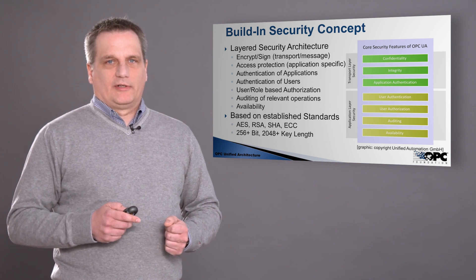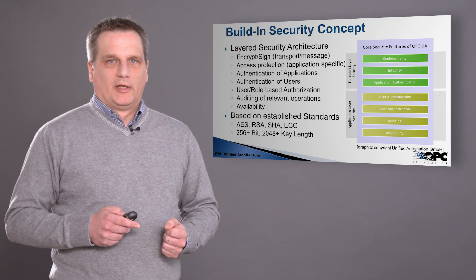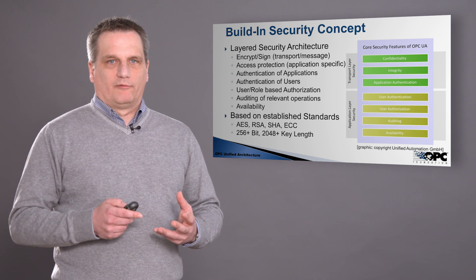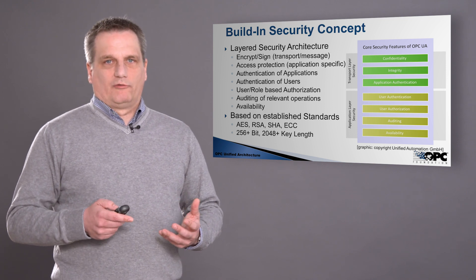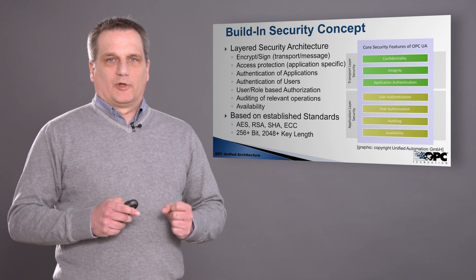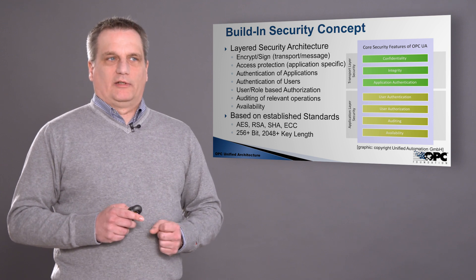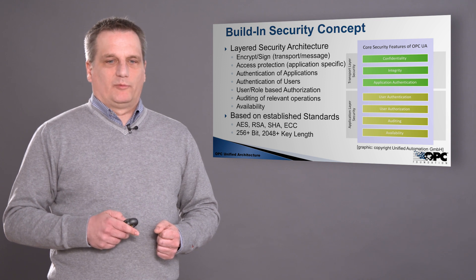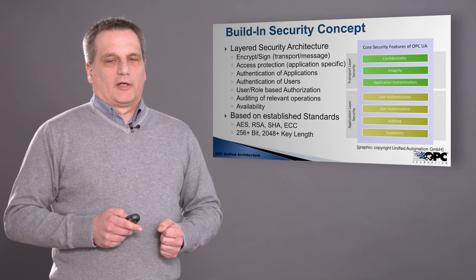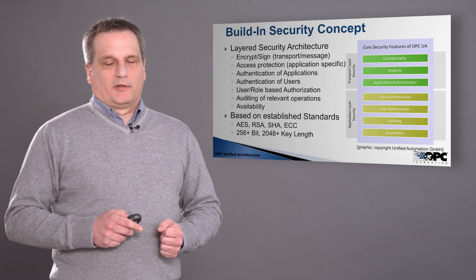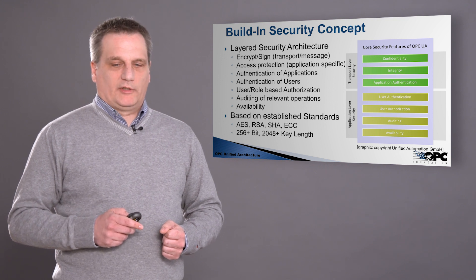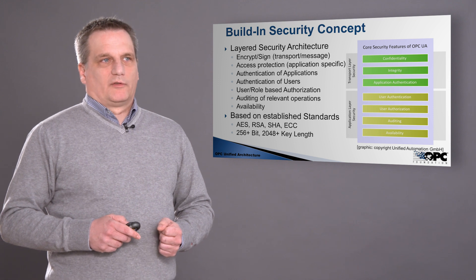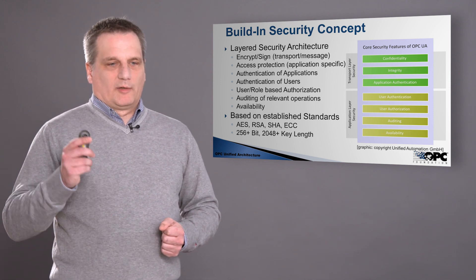In addition, there is an auditing system built into OPC UA. Any changes or modifications to the security of nodes are audited, and the server records this information so we can find out what happened and who changed what setting. The security of OPC is based on established standards: AES and RSA. We have SHA algorithms and we even use elliptic curve cryptography, with encryption depths of more than 256 bits and key lengths starting from 2048 going up to 4000, depending on the computing power of the device.